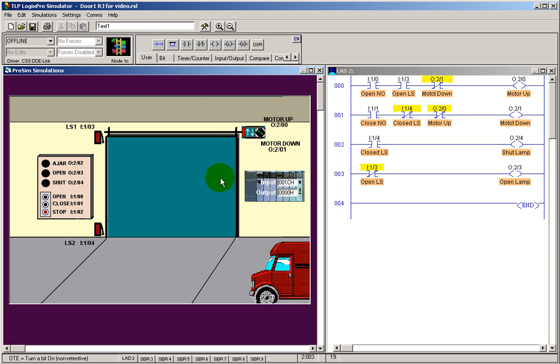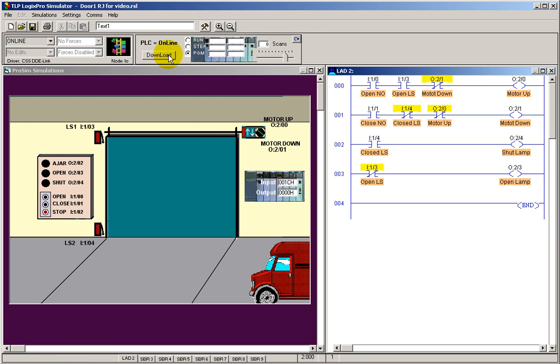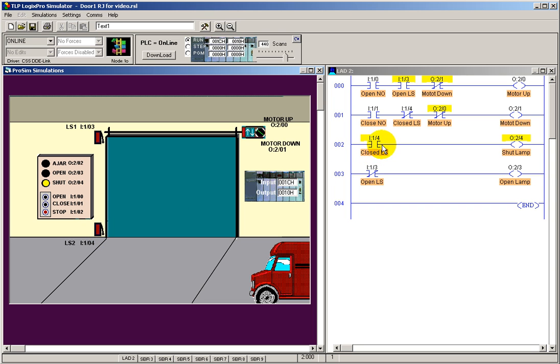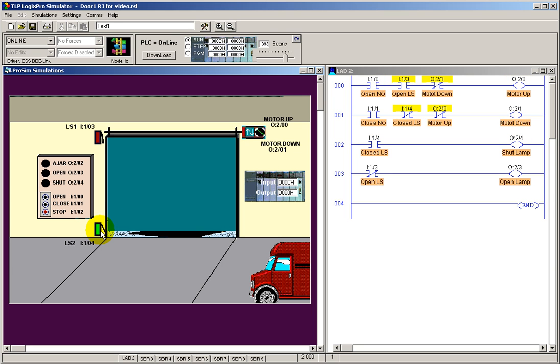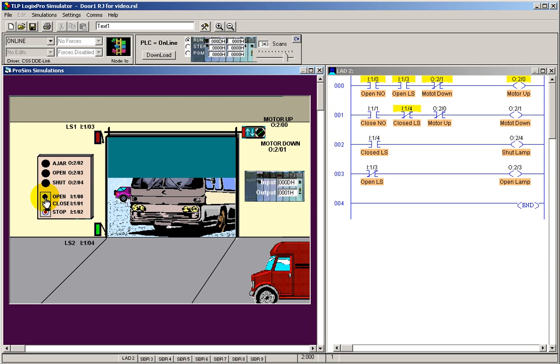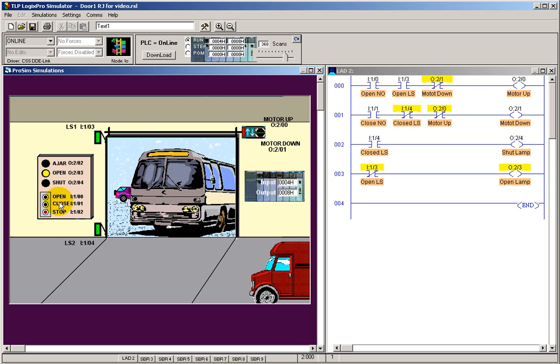Now let's try running this guy. Switch over here, download. You notice just when we start to put it in run mode, our shut lamp comes on because we're actually true in this statement here. That's the only thing that is needed to energize this shut lamp. We're closed, activating this limit switch and energizing the shut lamp. If we open just a bit here, we've no longer closed this switch. It's open, and that doesn't satisfy this condition anymore. Open limit switch is still not true either though until we go fully open. And then this is true. This is no longer activated. It's looking for that condition to be true and activating the open lamp. That's the door exercise one explained.